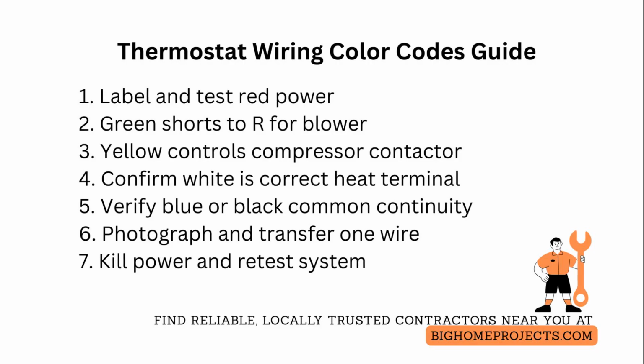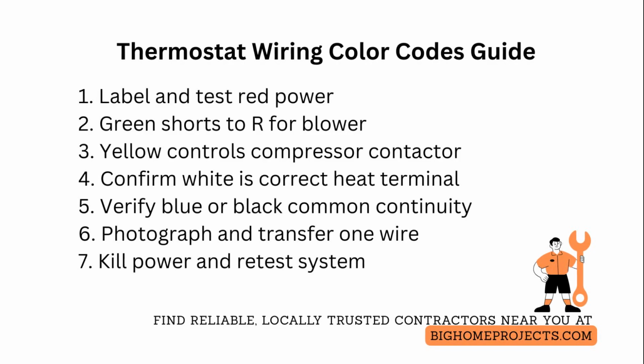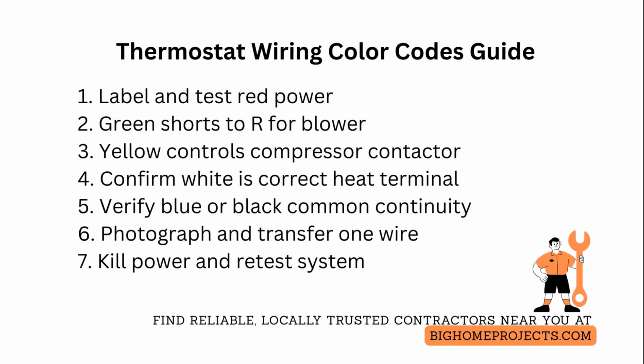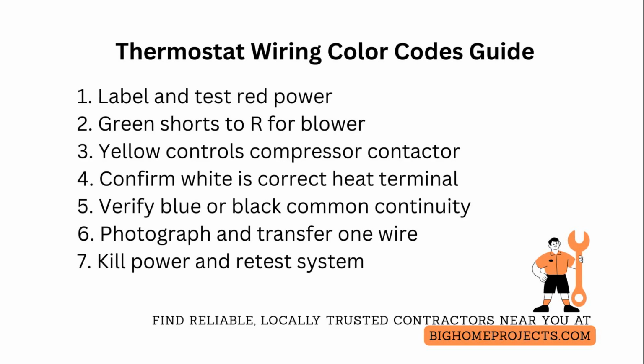Green goes to the fan relay and should energize the blower when you short it to R during a system test. Yellow controls the compressor contactor for cooling and must switch to common when the thermostat calls for air conditioning, so the condensing unit runs.